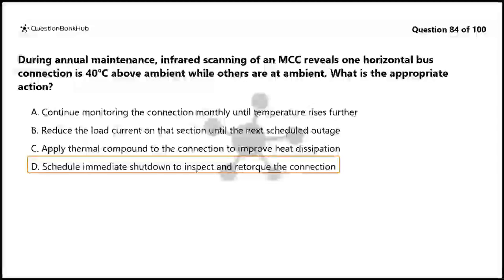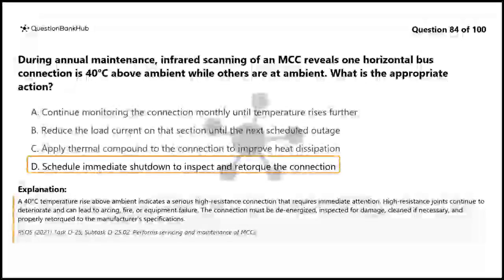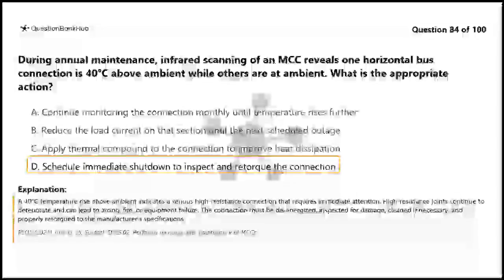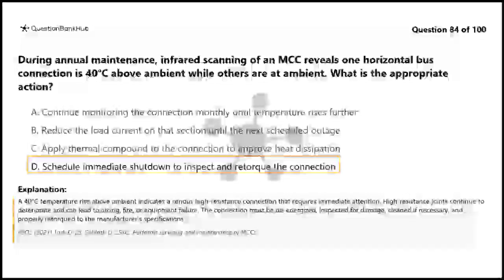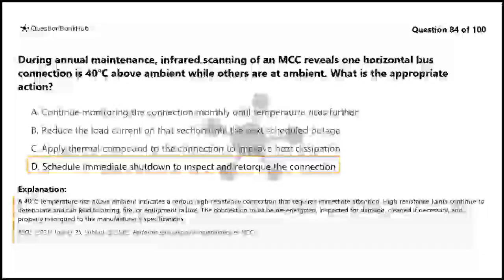The correct answer is D. Schedule immediate shutdown to inspect and retorque the connection. A 40 degrees Celsius temperature rise above ambient indicates a serious high-resistance connection that requires immediate attention. High-resistance joints continue to deteriorate and can lead to arcing, fire, or equipment failure. The connection must be de-energized, inspected for damage, cleaned if necessary, and properly retorqued to the manufacturer's specifications.